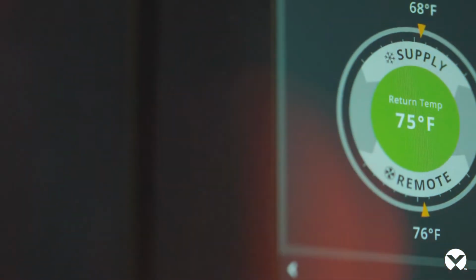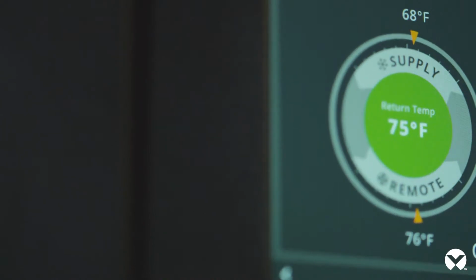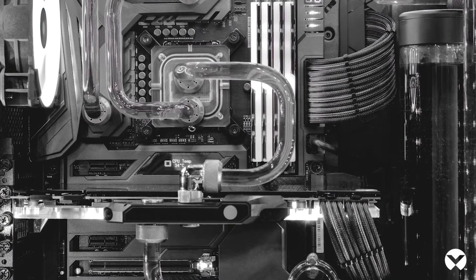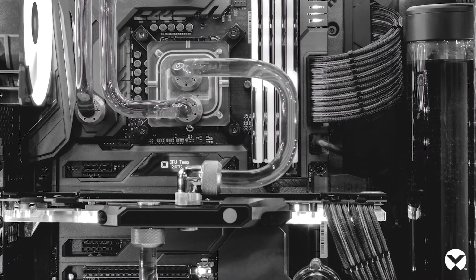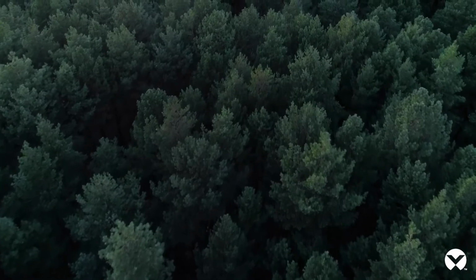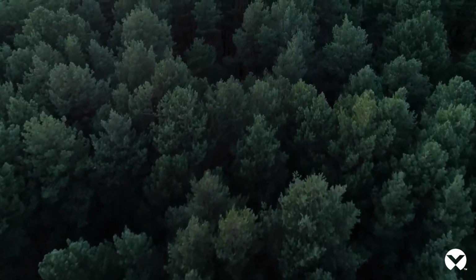With liquid-cooled servers, you have several more opportunities to incorporate free cooling. Instead of a server needing 70 to 75 degree air entering it, you're really cooling the chip or processor, which just needs to cool the junction temperatures, possibly over 100 degrees. So I need to bring a fluid in at a much higher temperature, and that allows me to reject the heat much more easily to the outside environment.